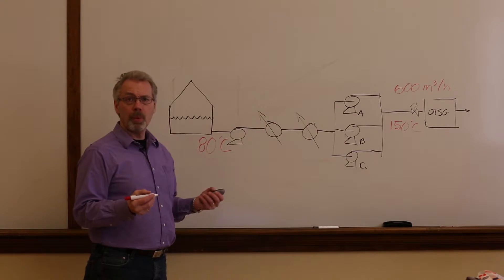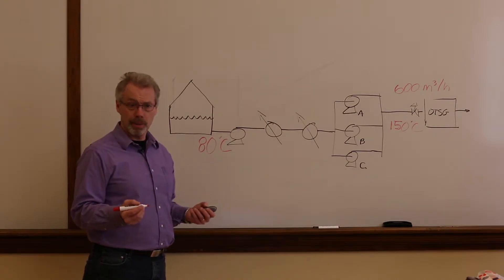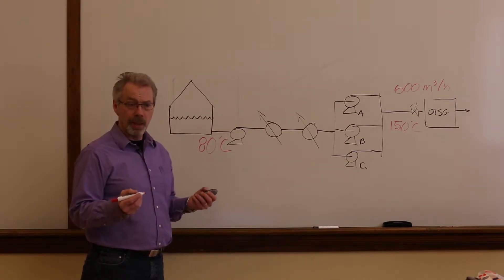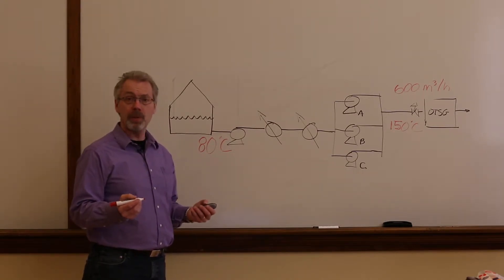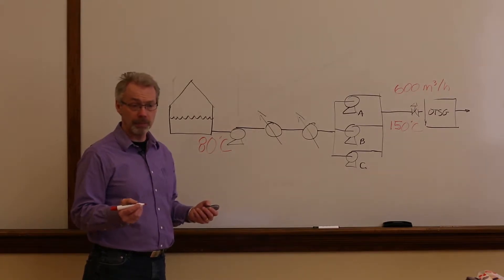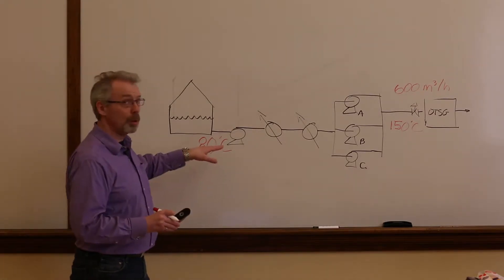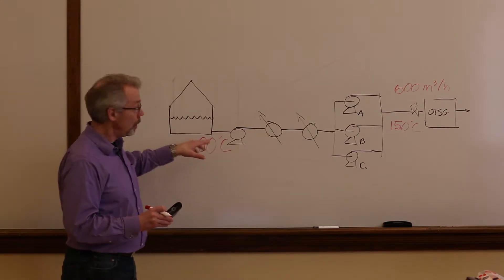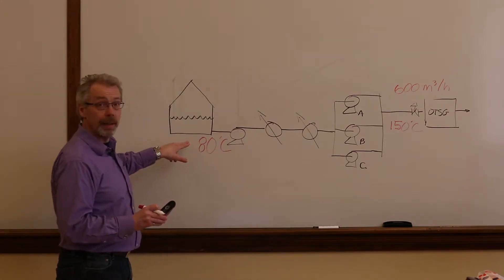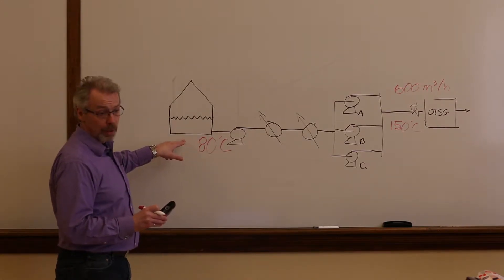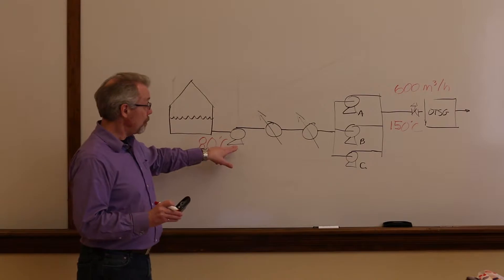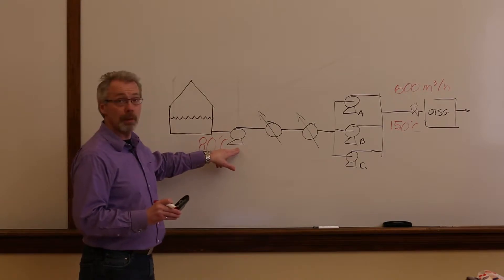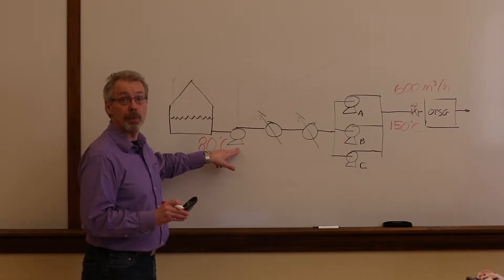So, what causes a sudden change in temperature? Let me explain a mechanism that I have seen in several operating plants. Here is a sketch of a typical boiler feed water system in a SAGD facility. Water at 80 degrees is stored in a tank and is pumped through a set of low pressure pumps to approximately 3000 kPa.